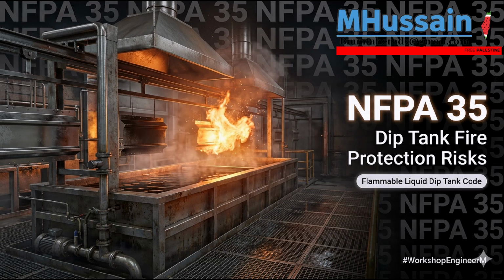Now, deflagration is a specific scientific term. It is. It means an explosive combustion wave that travels rapidly, but at subsonic speeds, slower than the speed of sound. If that pressure builds up inside a heavily reinforced, rigid concrete box, the concrete box will eventually fail catastrophically. It will shatter, sending massive lethal slabs of concrete and steel shrapnel flying in every direction. Just a giant bomb. Right. To prevent this, the building must be designed to intentionally fail in a controlled manner. This is deflagration venting. So you are literally building weak spots into the fortress.